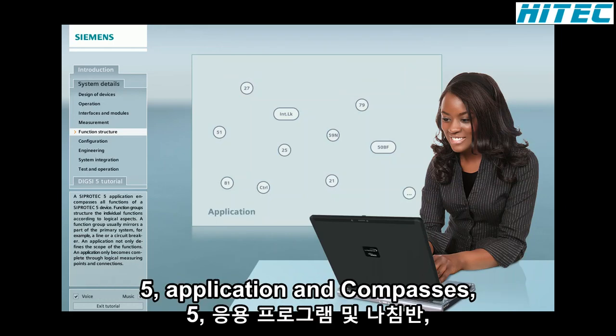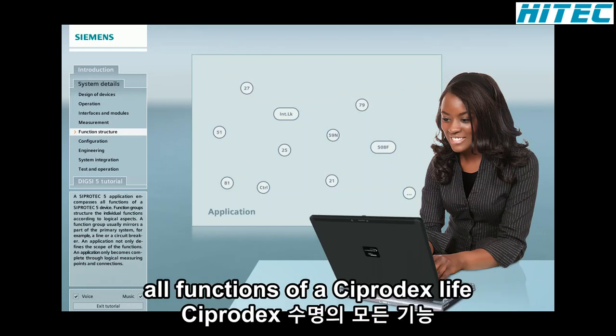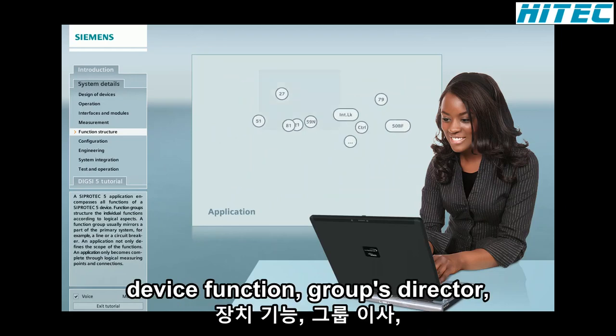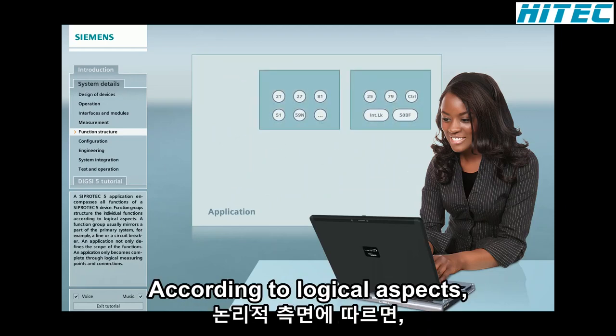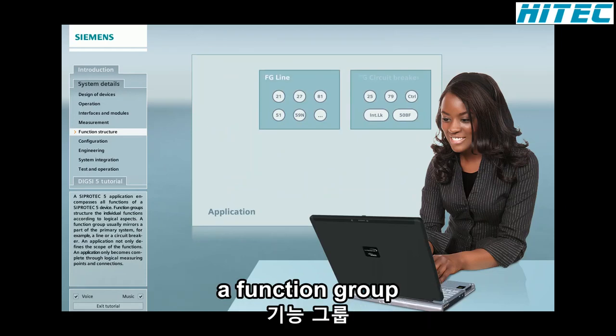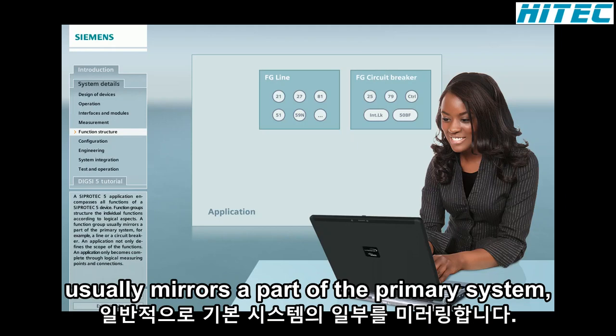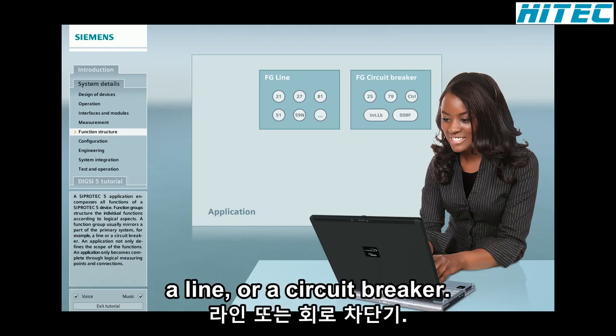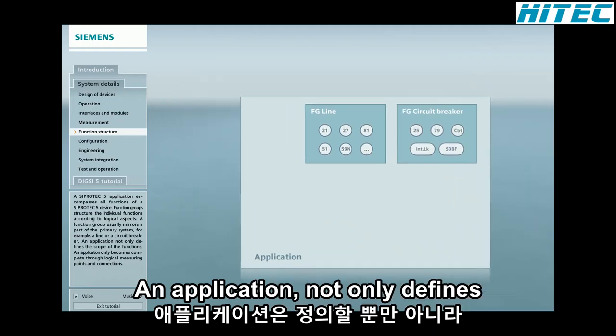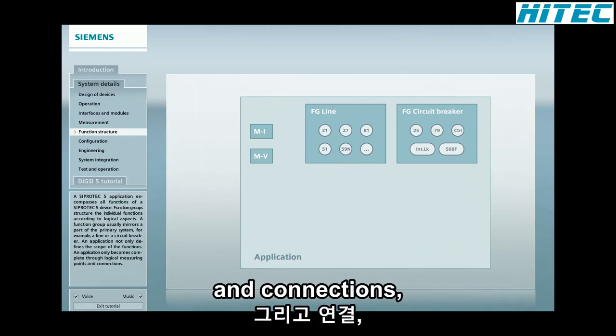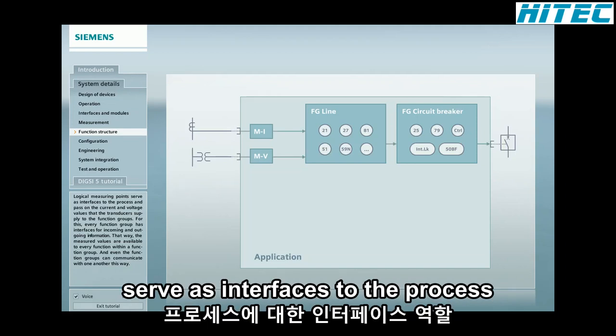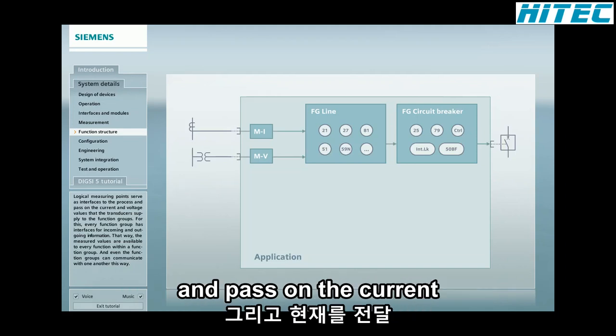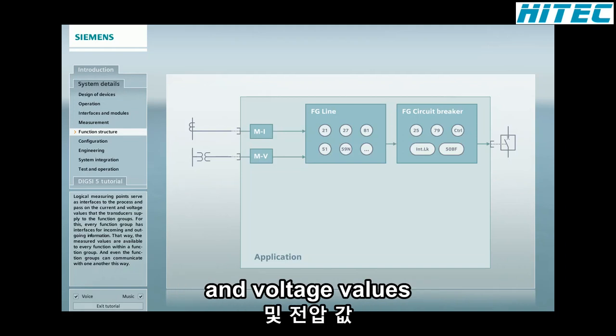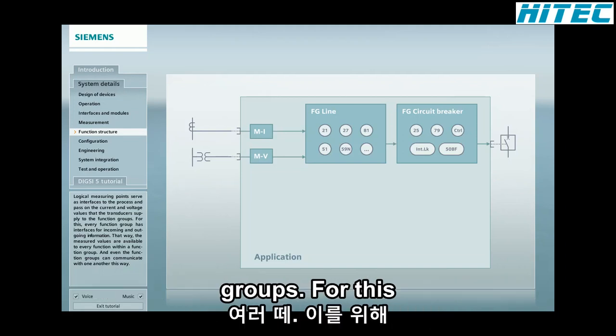A SIPROTEC 5 application encompasses all functions of a SIPROTEC 5 device. Function groups structure the individual functions according to logical aspects. A function group usually mirrors a part of the primary system, for example, a line or a circuit breaker. An application not only defines the scope of the functions, an application only becomes complete through logical measuring points and connections. Logical measuring points serve as interfaces to the process and pass on the current and voltage values that the transducers supply to the function groups.